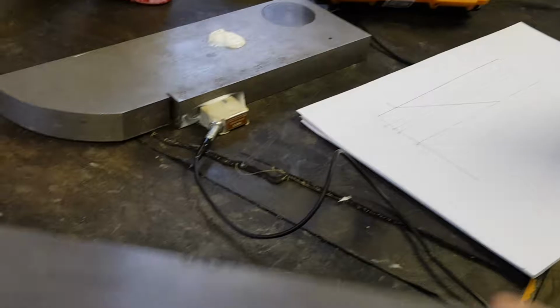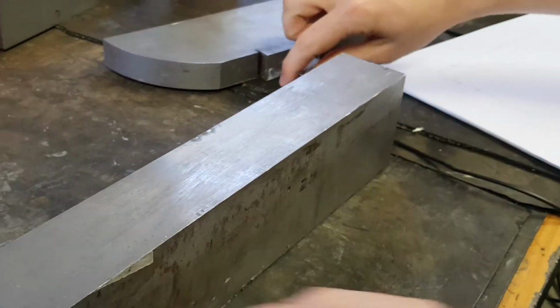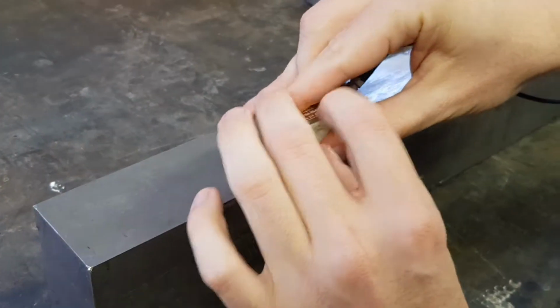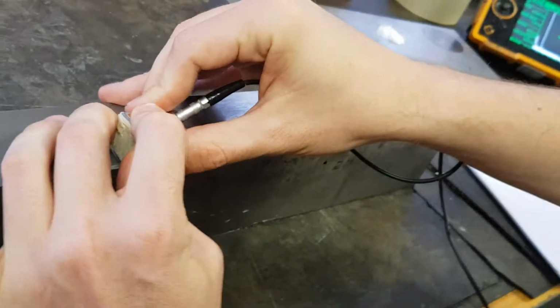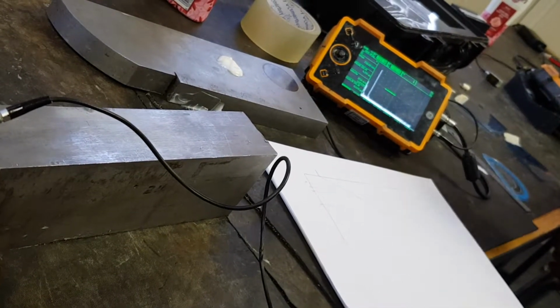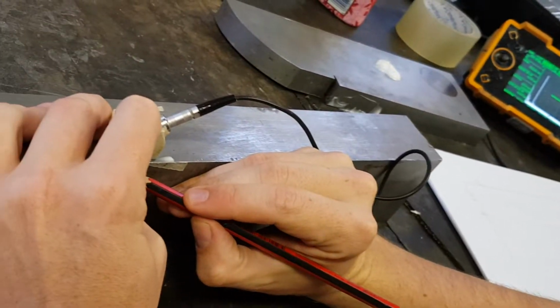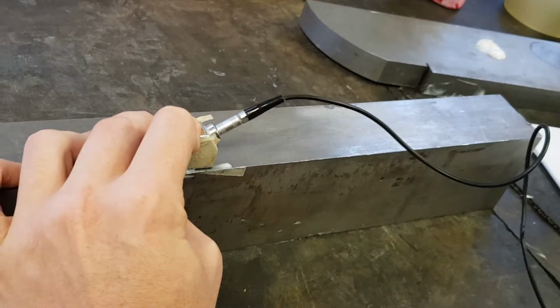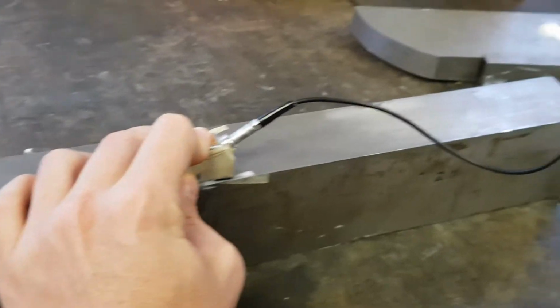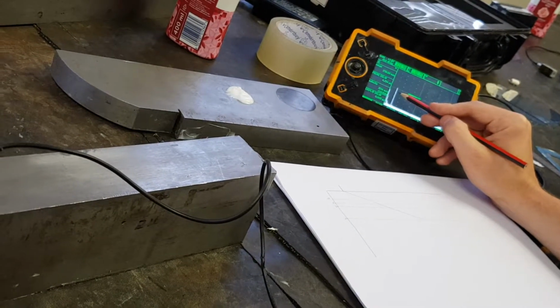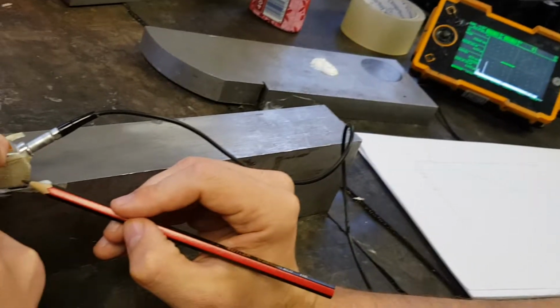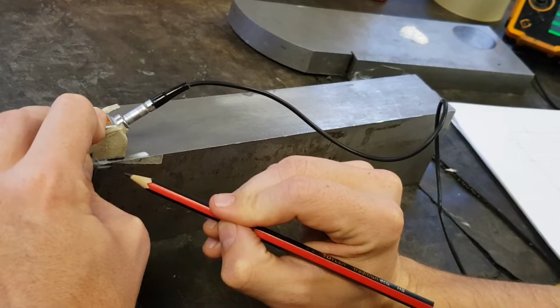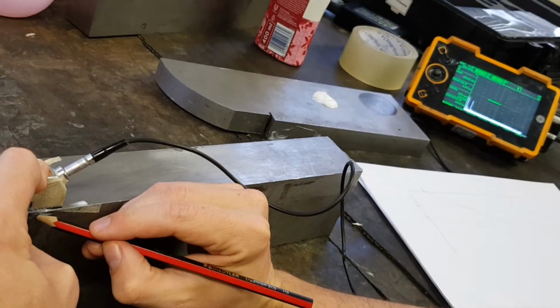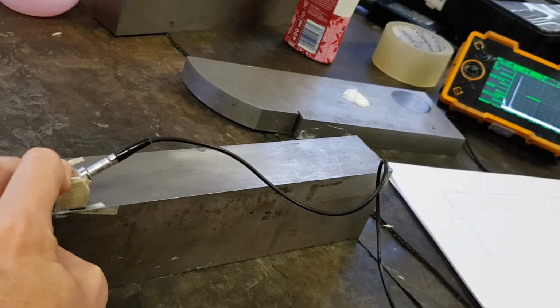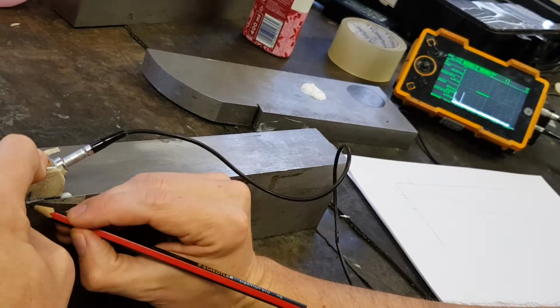Now what I'll do, we're going to do a 6 dB drop for now, but the 20 dB drop follows the same principle, just a little bit different. We'll put our probe on the block, once again find the 13mm hole, maximize it and adjust the dBs so it is 80% of our full screen height. On the block where the beam exit point of your probe is, you make a mark. You move your probe forwards laterally until the echo reaches 40% on your screen. Care should be taken so your probe stays perpendicular with the sides. Don't squint it, just move forward. Where it's 40%, you make another little mark at your beam exit point. You move it back up until 80, down to 40 again, and make another little mark on your block. You can now remove your probe.